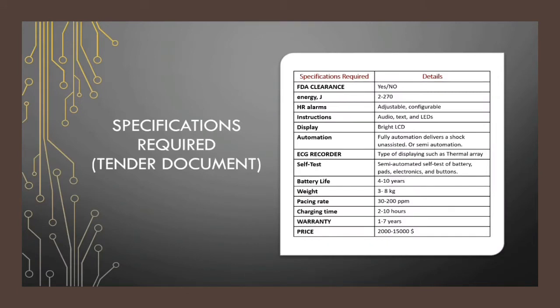This is our tender document. The specifications required, such as FDA clearance, energy range, the instructions, type of display, screen, automation, ECG recorder, self-test, type of battery and the life of battery, the weight of the device, the price and warranty. Based on the comparisons, we choose Philips Healthcare Heart Start for our hospital, and the other two options are backup.